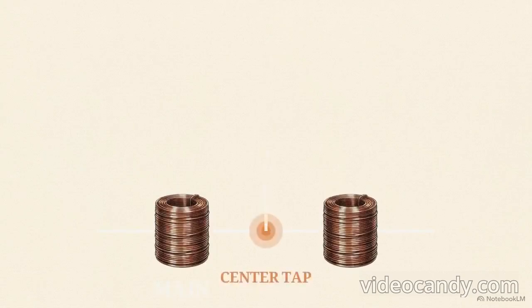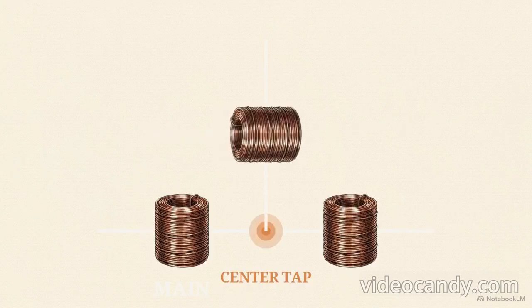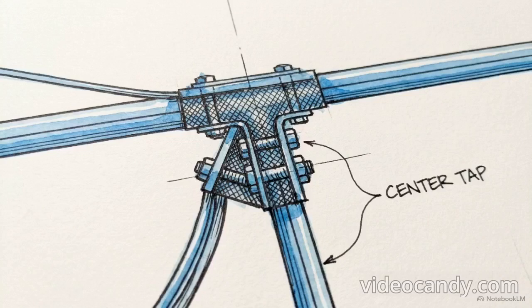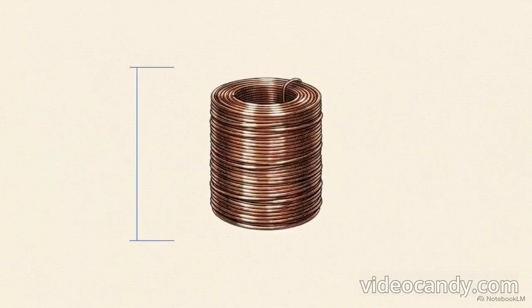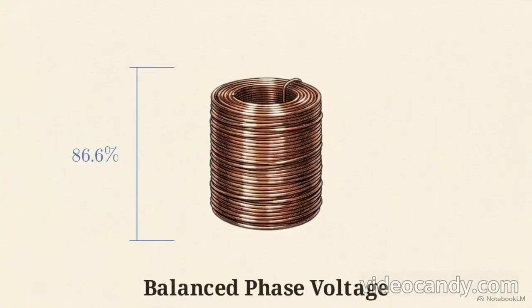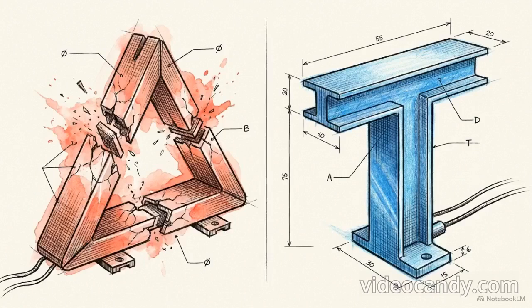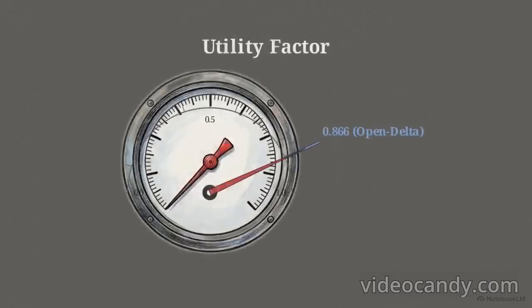When true 3-phase power needs to be converted into an isolated 2-phase system, we use Charles F. Scott's T-T connection. The setup requires 2 transformers. The horizontal main transformer is built with a precise center tap on its primary and secondary windings. The vertical teaser transformer connects directly to that center tap. To ensure balanced phase voltages, the teaser's windings must be designed to handle exactly 86.6% of the line voltage.